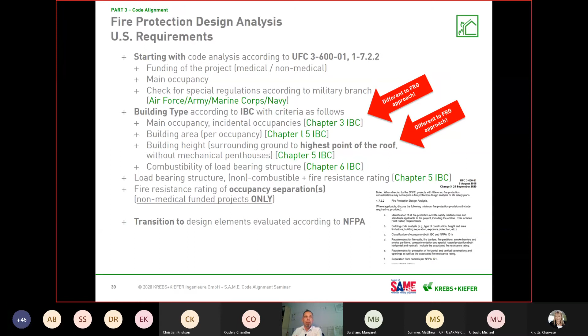The cut between working with IBC and NFPA comes when defining the occupancy and the occupancy separation. The fire resistance rating of occupancies in medically funded projects is done in NFPA 101. For non-medical funded projects, we're with IBC. But there are still some similarities. NFPA 101, chapters 11 to 45: there are a lot more occupancies defined in NFPA than we have special building codes and guidelines for occupancies in Germany. But that's always a good place to start and to see where you can align codes with the occupancies.